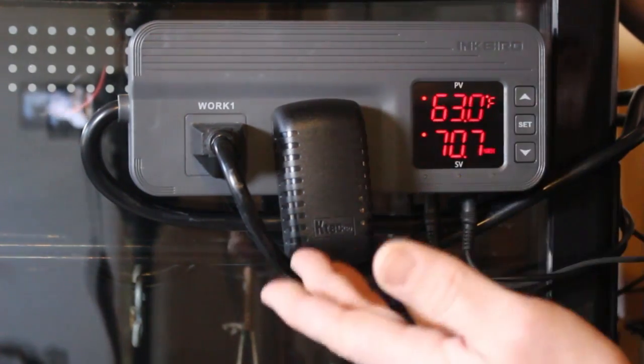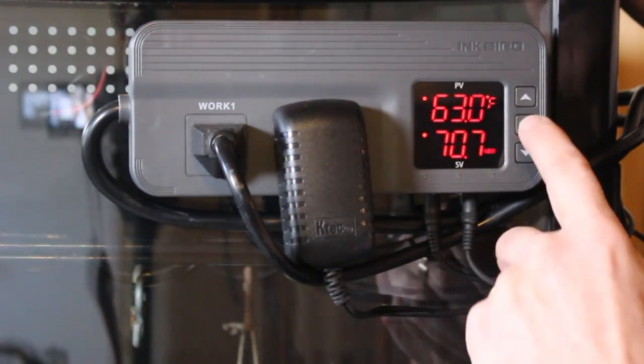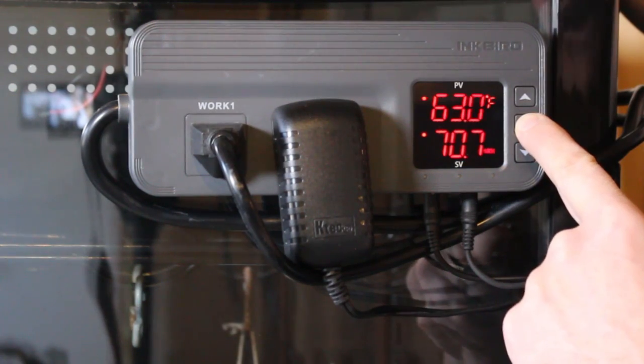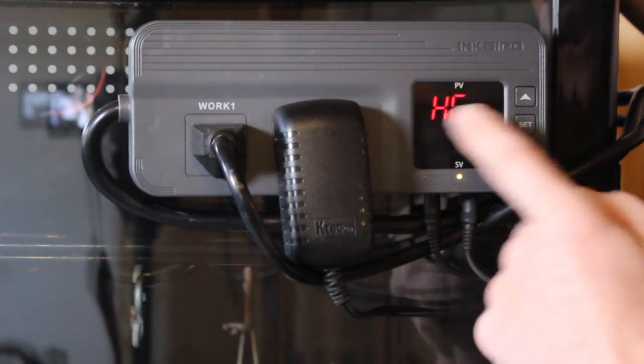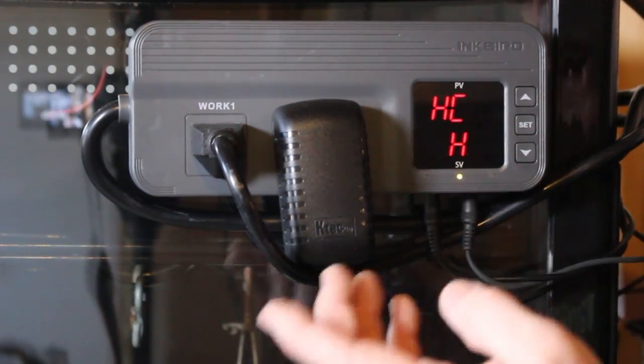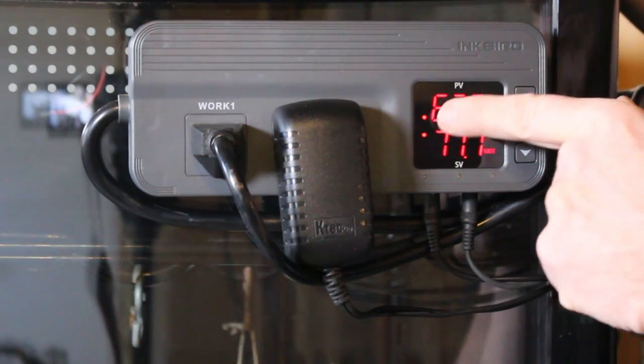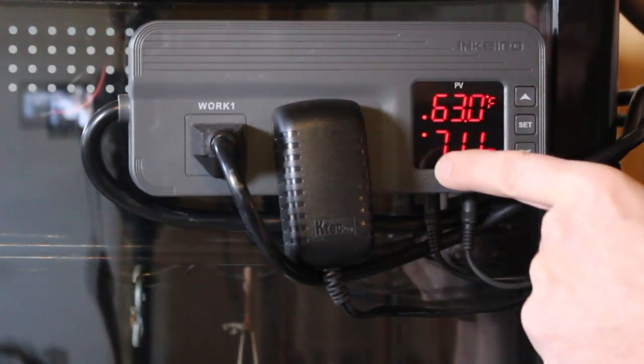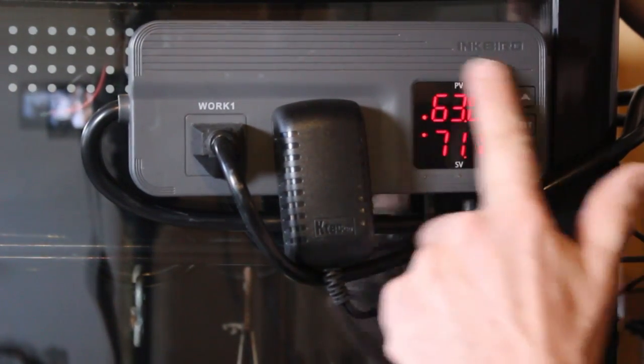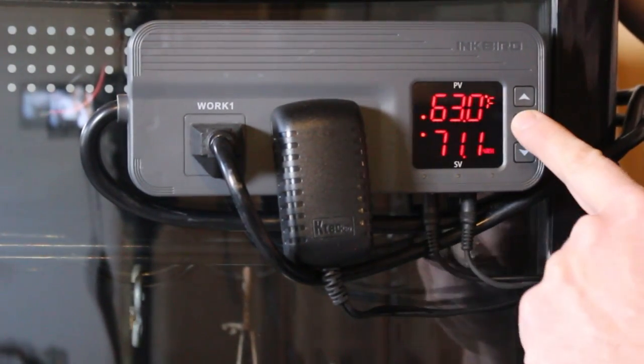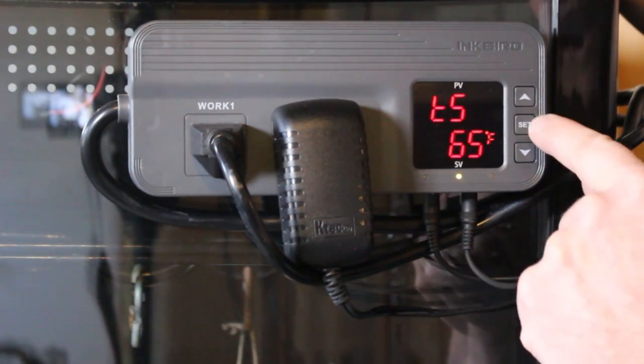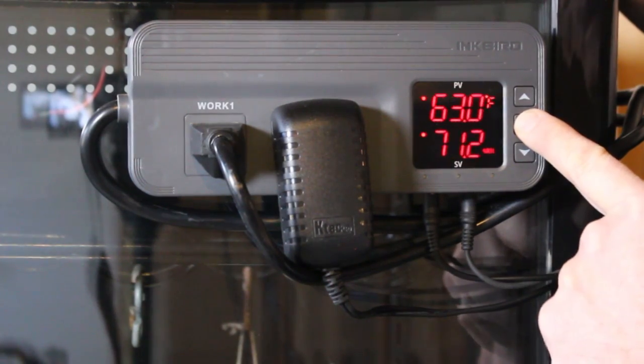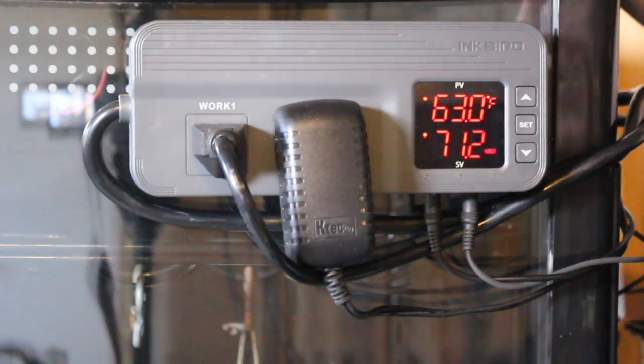If you were to set this up to control a heater, how would you do that? Well, hold down set, right? We want to control a heater. This isn't going to make any sense on my refrigerator. Temperature, set, heating, cooling, turning it into a heating device. And then just hold the button down. And look, this has changed. So it now knows that it's a heating device. But just to give you an example of how you can really quickly read this standard display here, let's set that back to cooling, lest we forget. Temperature, set, cooling, set, hold down set. And there, you can make a real quick temperature or any kind of setting change.